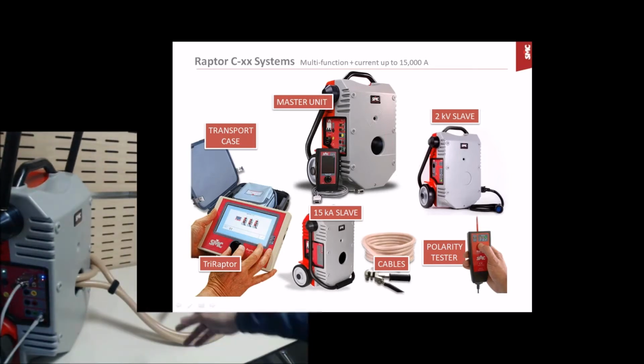And we have the injection cable. In this case we are doing an additional turn around the unit to produce a higher current. I will let you know why a little bit later. And these are the connections to one of the phases of the circuit breaker. The Raptor system is a single phase system, although we can also build a three-phase version by using 3 of these units. 3 master units can configure a three-phase system.